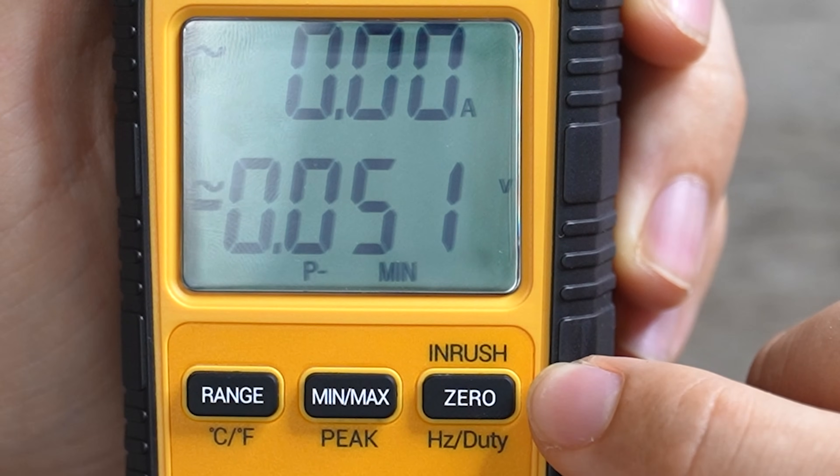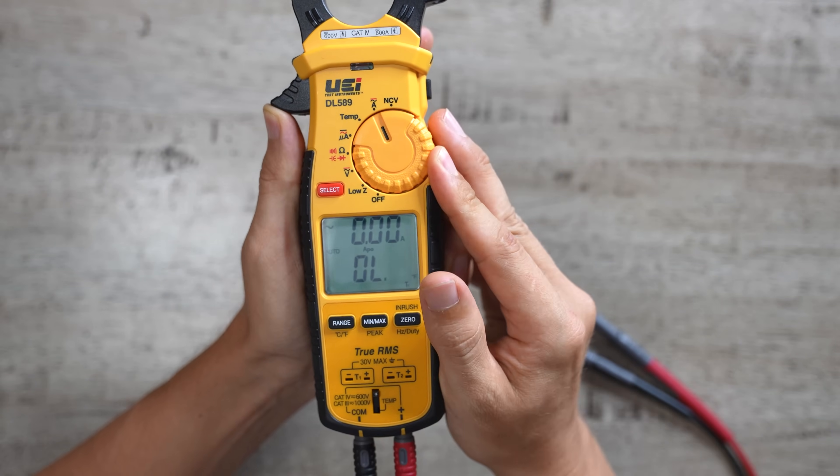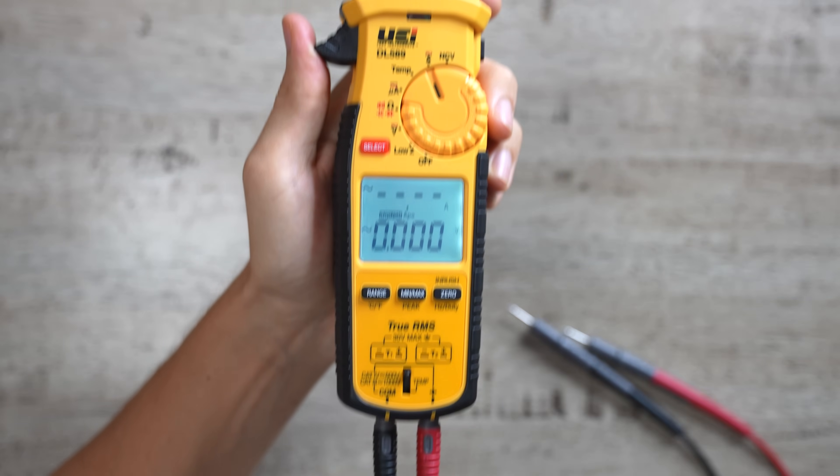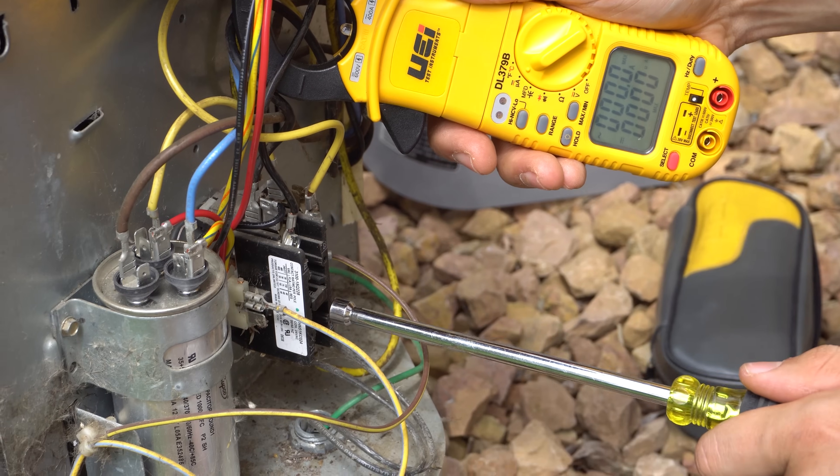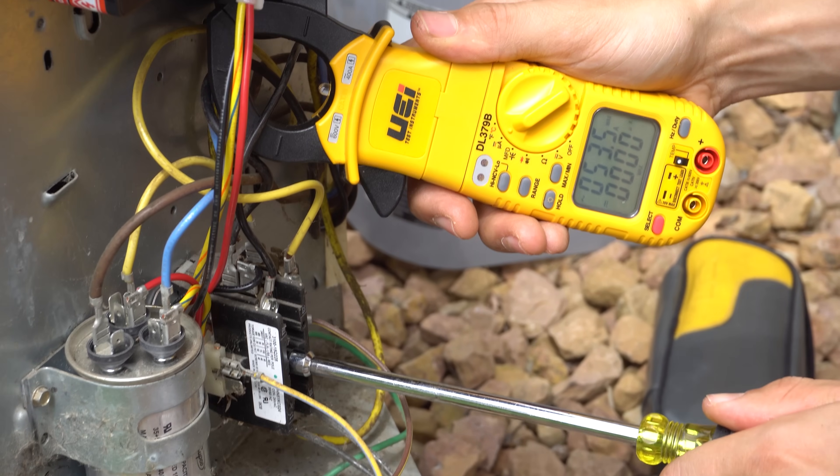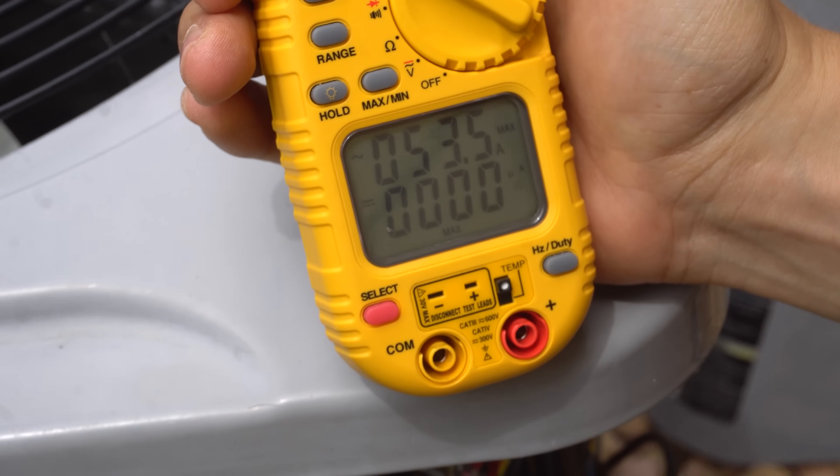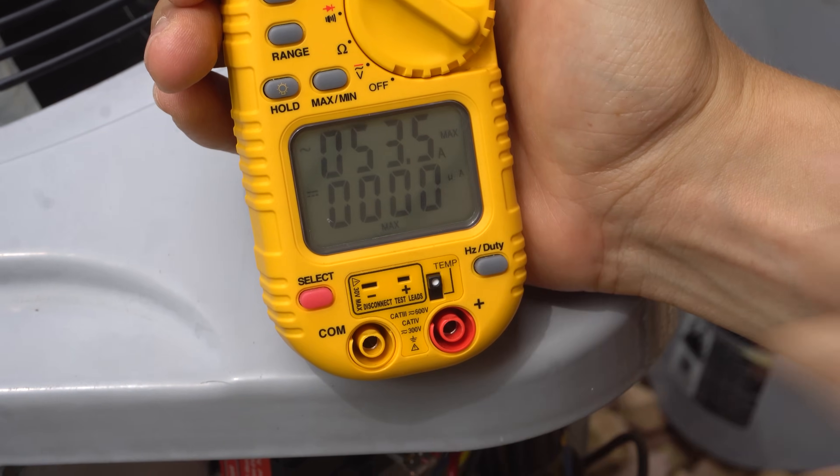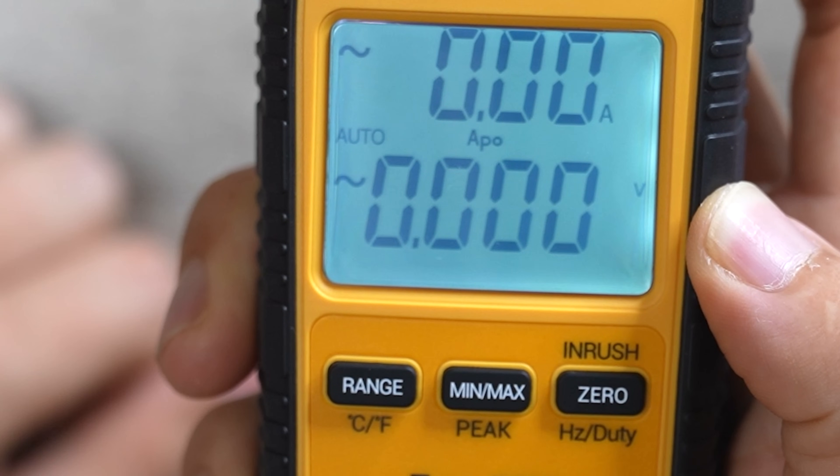Next up, we have inrush current, which can only be used when the meter is set to the amp setting. The inrush option would be used to check amperage when motors start up, because when a motor is starting, it draws a lot more amps than it usually does while it's running. So if you're measuring amperage and your meter is set to inrush, your meter is going to catch the highest spike in amperage right when that motor is starting up. This test is useful to see if a motor or compressor is drawing locked rotor amps.